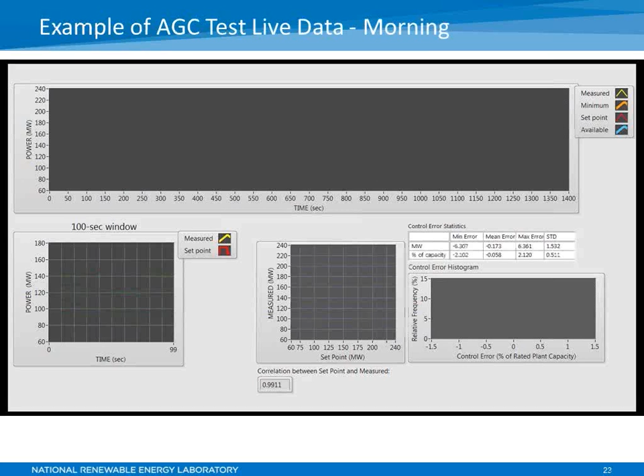This is an example of an AGC test during the afternoon ramp when the solar resource was actually varying. You see certain periods of time when a cloud was moving over the PV plant and the available resource is declining and then coming back. Even under such conditions, the plant is capable of maintaining that 30 megawatt headroom very well, and also following the scaled down AGC signal. The XY graph on the bottom shows correlation between set point and measured active power for different times of the day. Each color represents a different time of the day. You see it's very linear with a very high level of correlation.